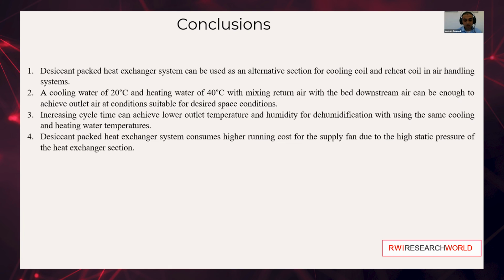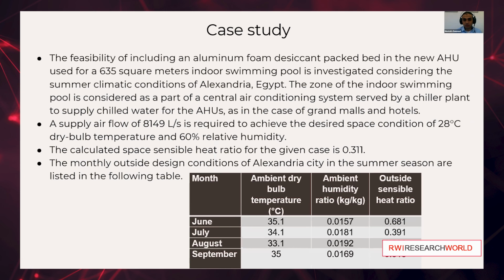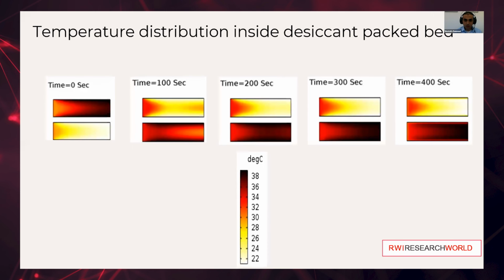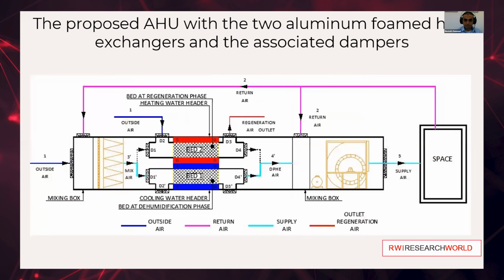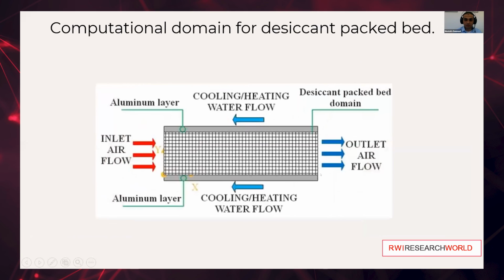Desiccant packed heat exchanger system consumes higher running cost for the supply fan in the air handling unit. This is due to the high static pressure for the air inside the bed due to the narrow passages left for air in order to proceed to the supply fan.